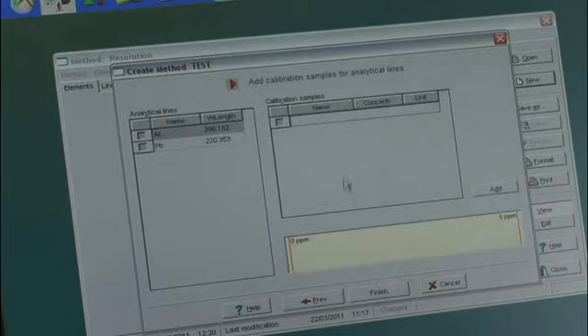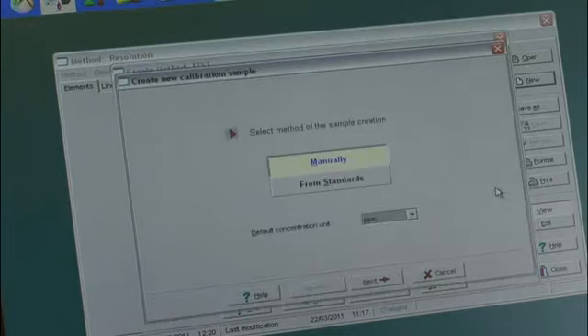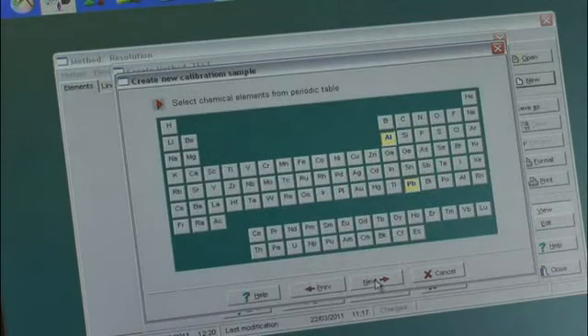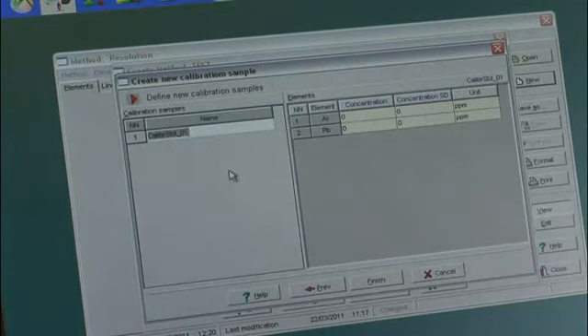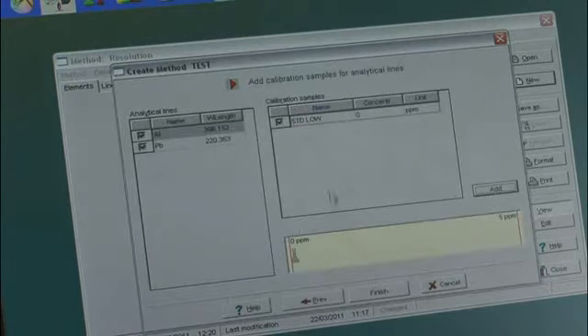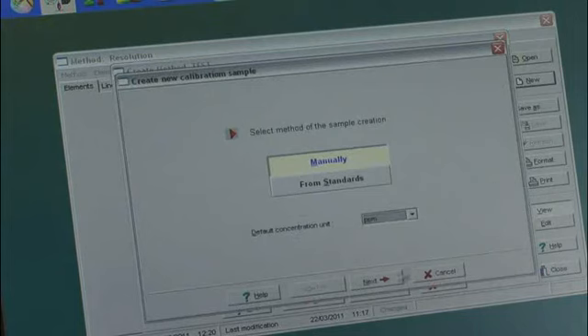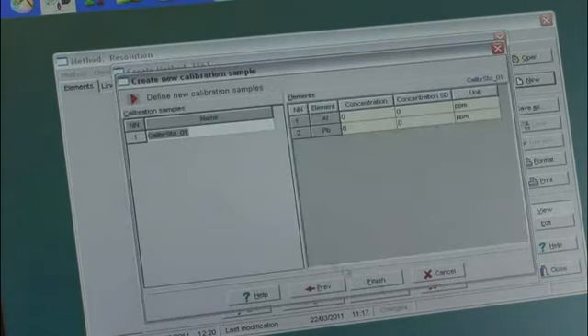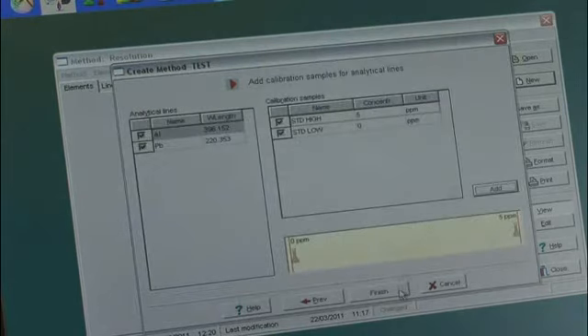Here's where I add my standards, so I'm going to say add, manually, ppm. Both of these are in my standard, so I'll leave them, and I'm going to call it standard low, and here I'm going to put the concentration, which is 0, so that's done. And then I'm going to add another standard, and I'll call this standard high. And I know my aluminum is 5 and my lead is 10. And that's all I'm going to do, just a blank and a high.